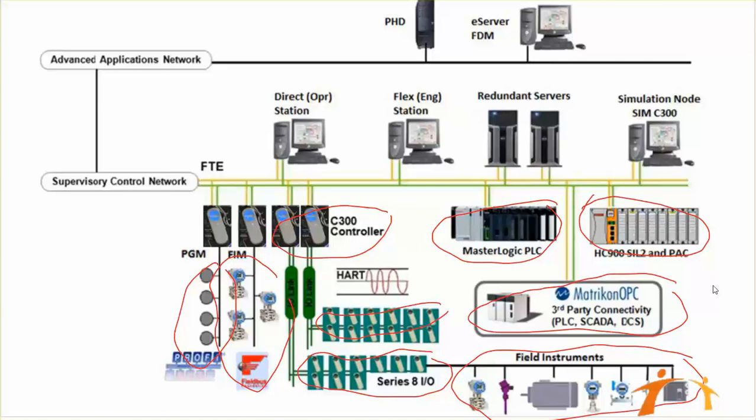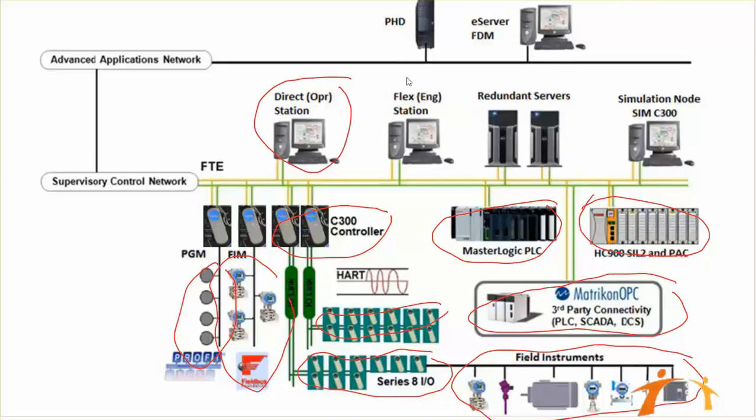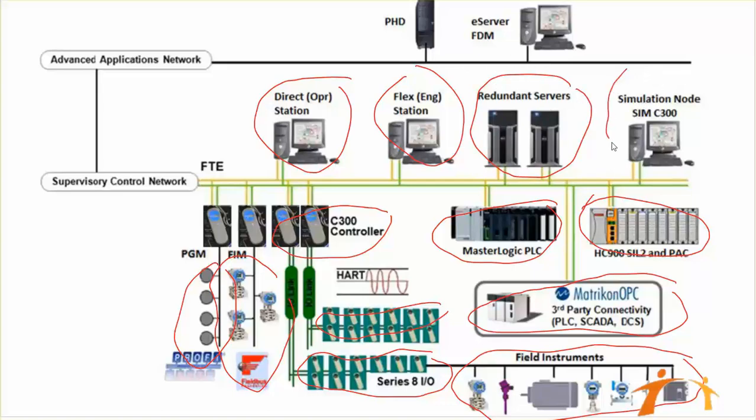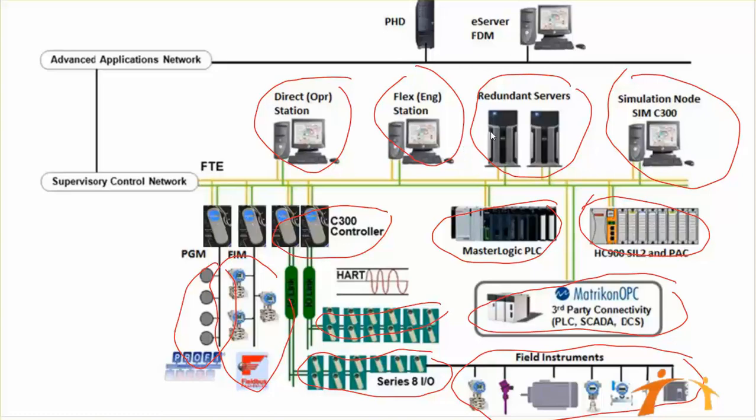That FTE network is connected to the next layer. What we can have on this layer: we can have our console station here, flex station, redundant server, and also a simulation node SIM C300. This is where we actually simulate your actual field process in a simulation environment. You practice it, you verify your process. It is especially made for operators and process engineers. They simulate everything here and then implement it to your servers and engineering station.